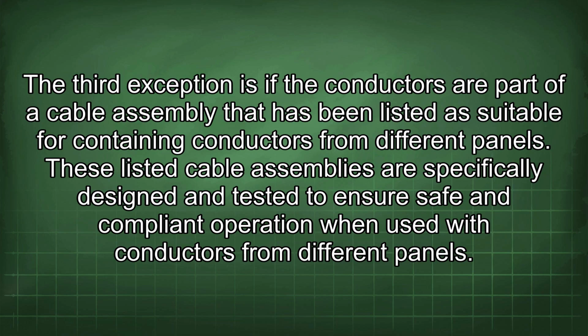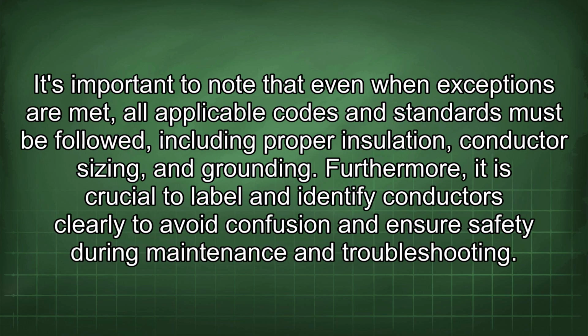The third exception is if the conductors are part of a cable assembly that has been listed as suitable for containing conductors from different panels. These listed cable assemblies are specifically designed and tested to ensure safe and compliant operation when used with conductors from different panels.